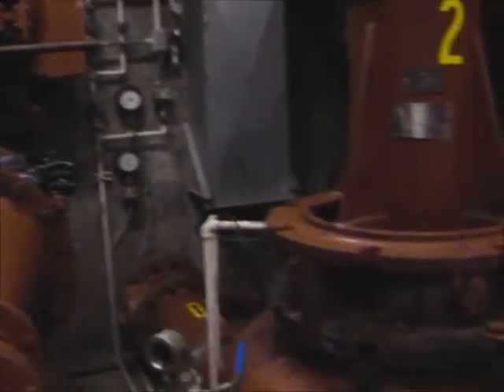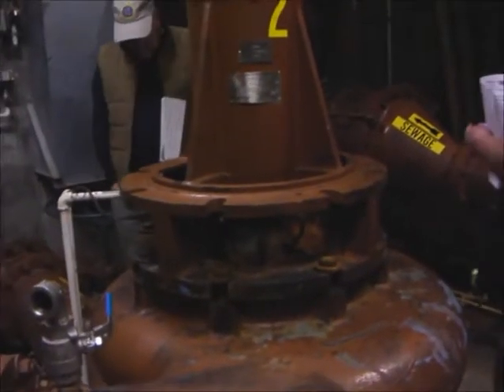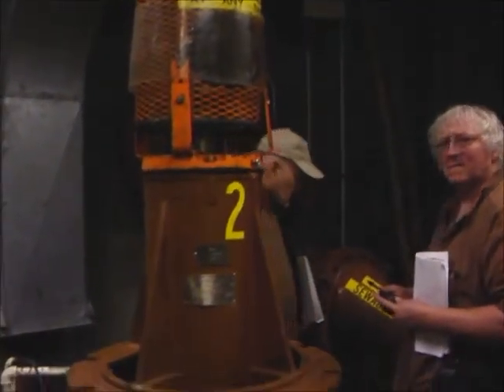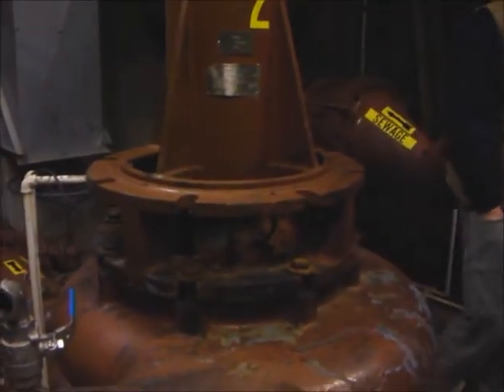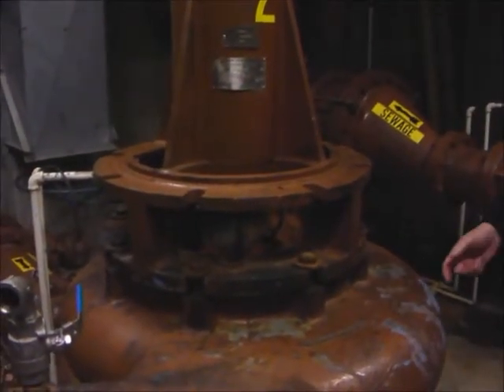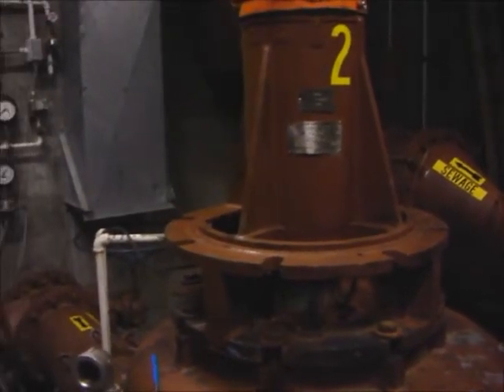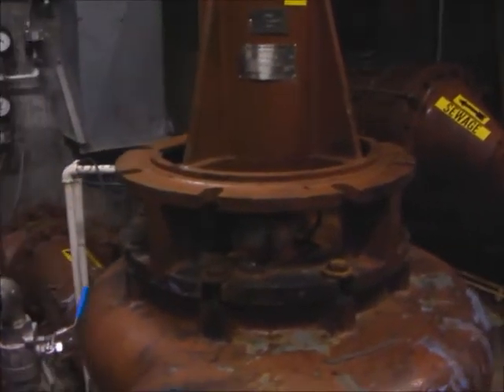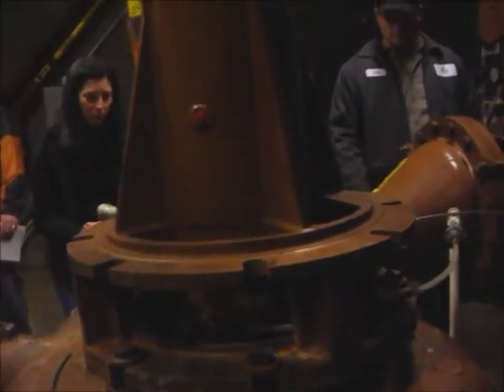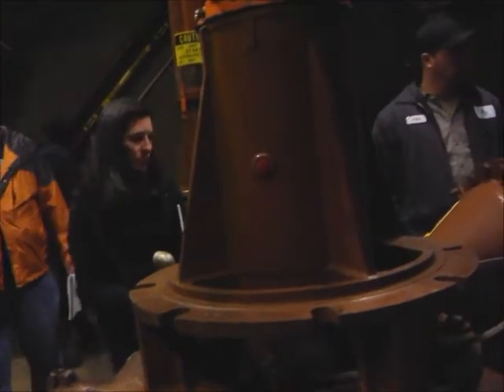These pumps have mechanical seals. Water has to be supplied to the mechanical seal, or else it just destroys the seal, and then you have sewer leakage coming up here. So that's why we have a water line hooked up to the pump. Every time the pump's on, it tells the seal to open up the water valve and it's metered into the seal to keep everything lubricated. Without that, you're looking at a $1,200 seal when you're destroying it. It doesn't actually come on until it gets to a certain level, right? Yeah, it's pressure. That's why they're dry right now.